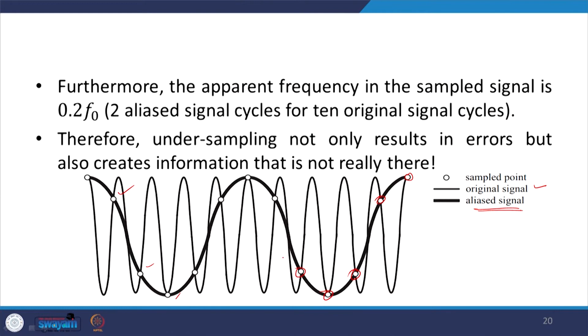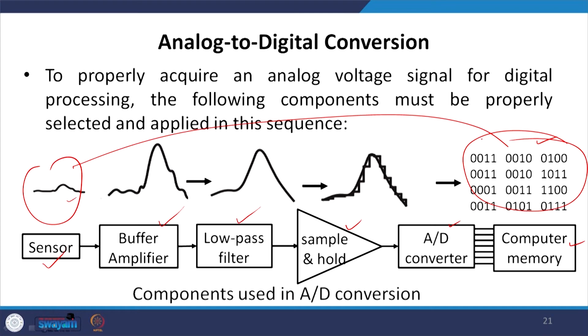Then, to properly do the analog to digital conversion, that is, to properly acquire an analog voltage signal for digital processing, the following components must be properly selected and applied in this sequence. For example, the sensor gives an analog signal. You need a buffer amplifier in order to amplify that signal. Then you need a low pass filter, then a sample and hold device, and once you have the sample and hold device, you need an A to D converter, and then this can go to the computer memory, and this way you can convert your analog signal into the digital signal.